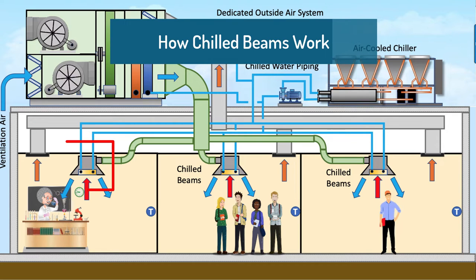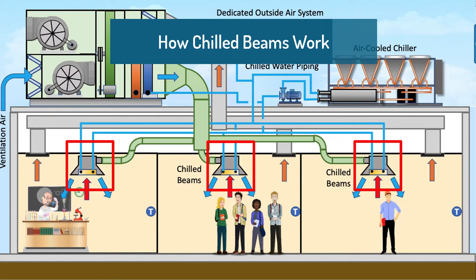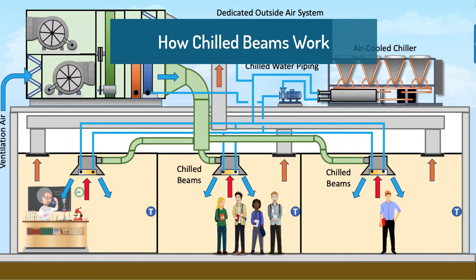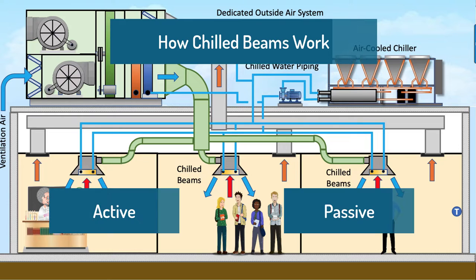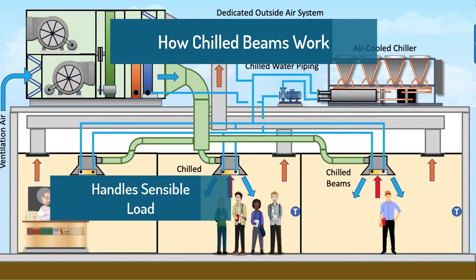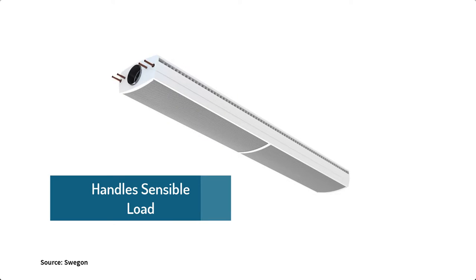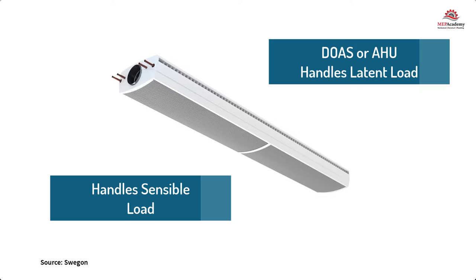The use of chilled beams allows for a reduction in the size of air handlers and chillers, as less primary air is served to the space and higher temperatures of chilled water are used for cooling. Chilled beams are either of the active or passive type. The chilled beam will take care of the sensible requirements of the space, while the dedicated outside air system or air handler will handle ventilation requirements.